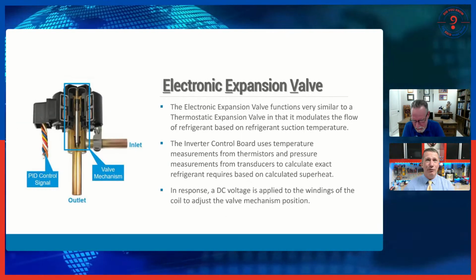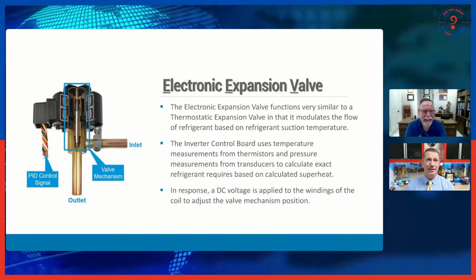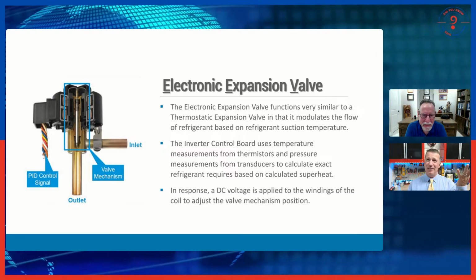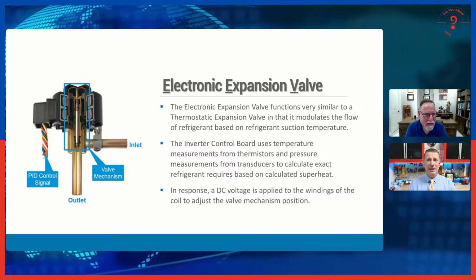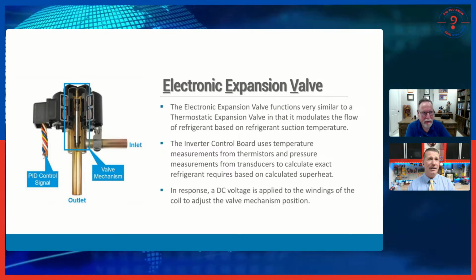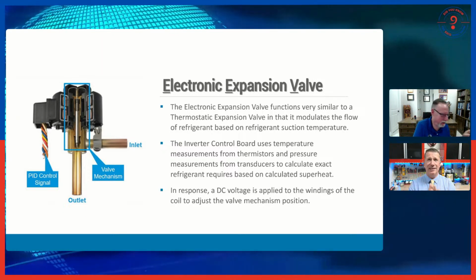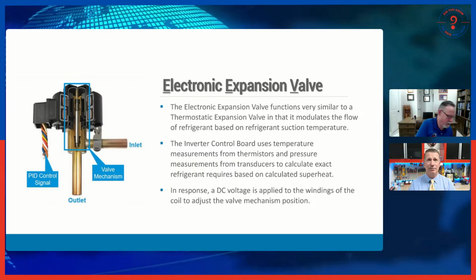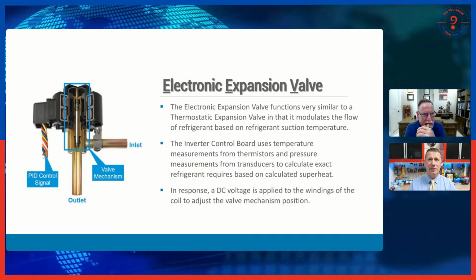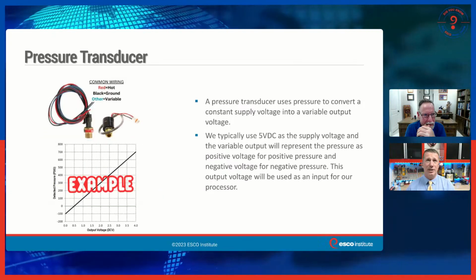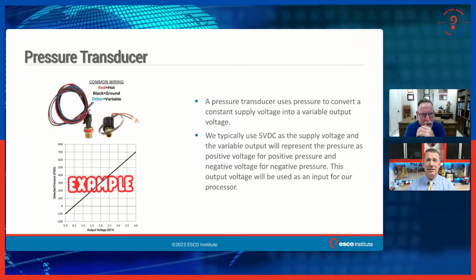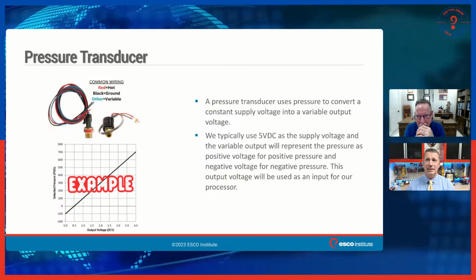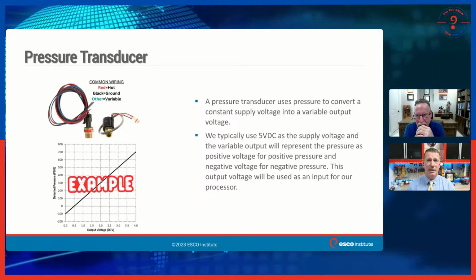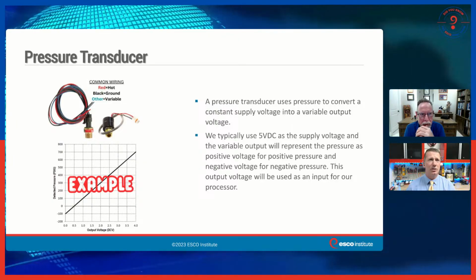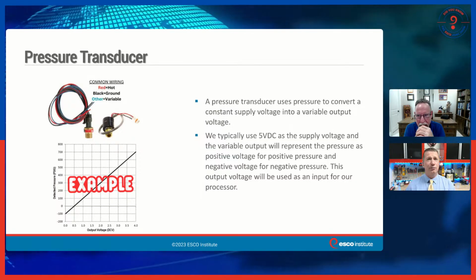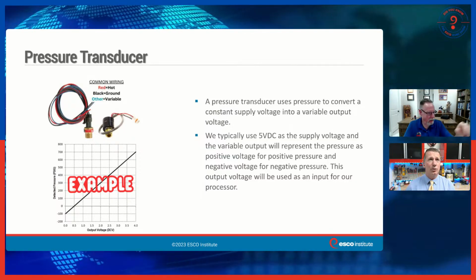So if we put that into principle and understand how that inverter control operates, then it's just a matter of some additional inputs and outputs. Think about an electronic expansion valve. If I have an HVAC system with that electronic expansion valve, all we're actually doing is just a metering device, a full standalone operation of the system. A lot of times it's not even tied into that inverter control board, it's tied onto just a separate power supply with maybe some thermistors, and sometimes uses a transducer for the signal.